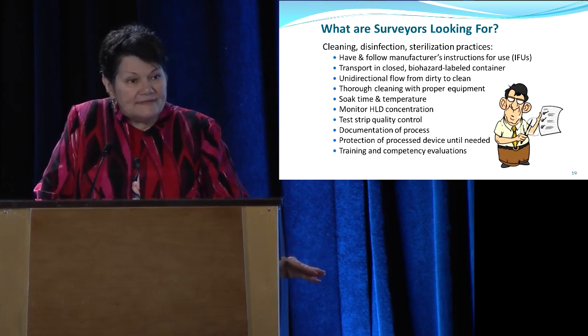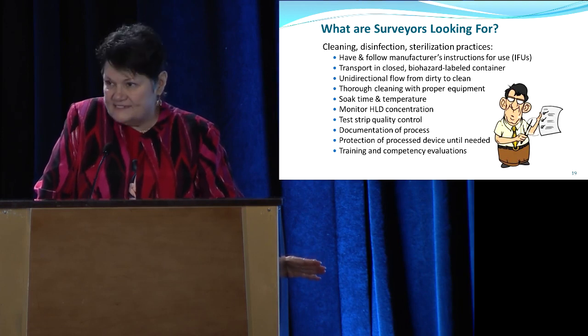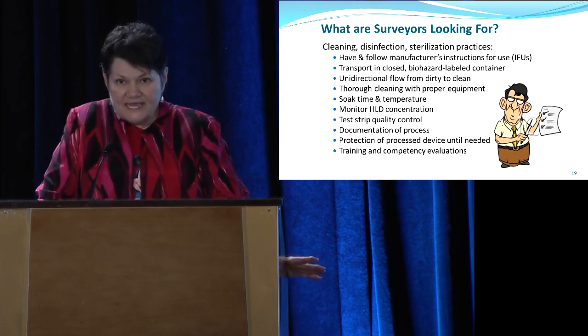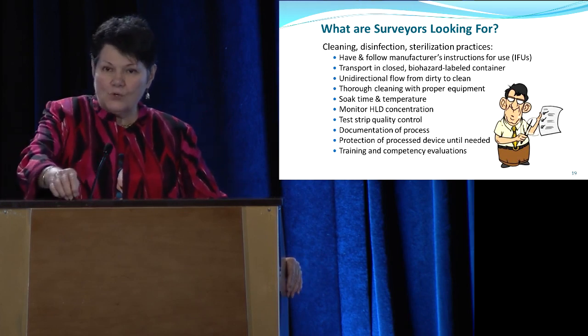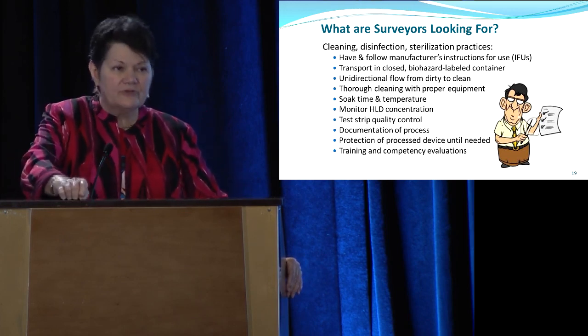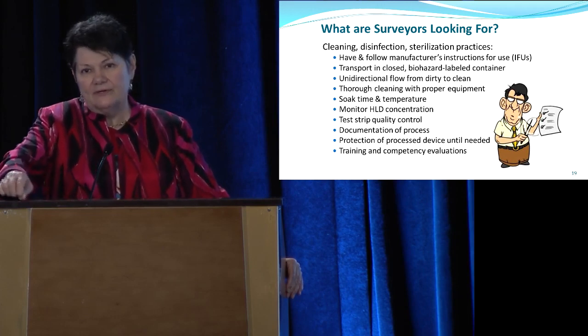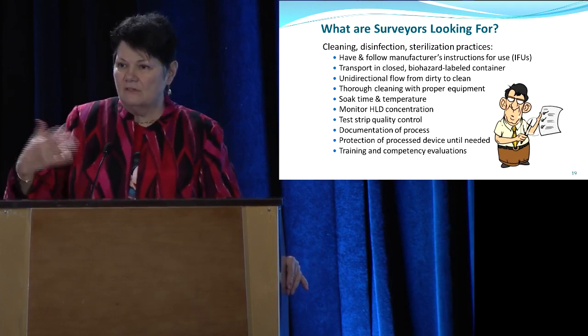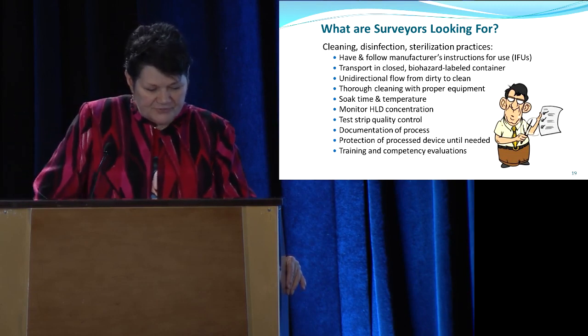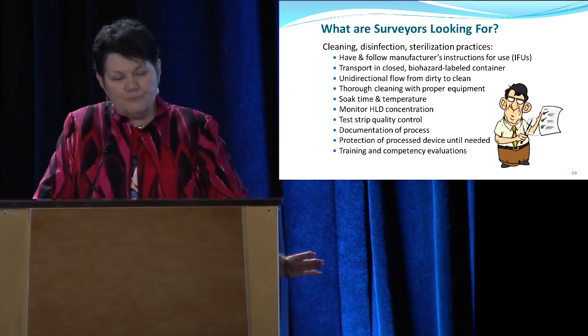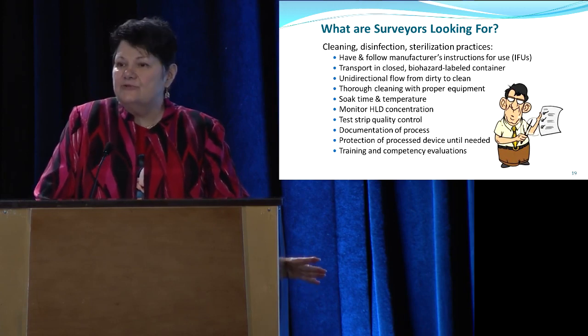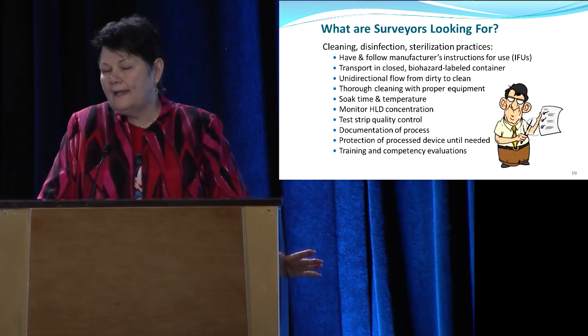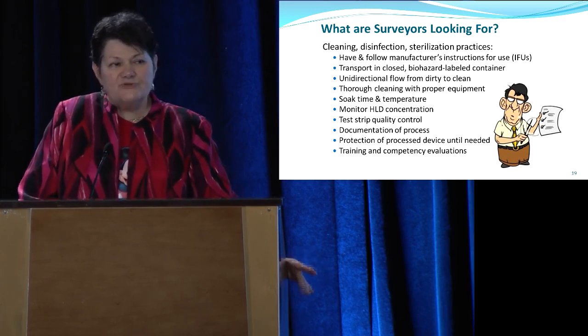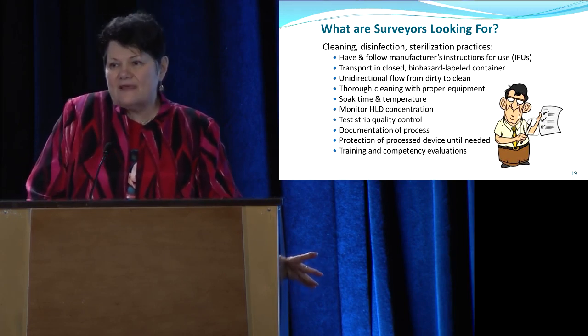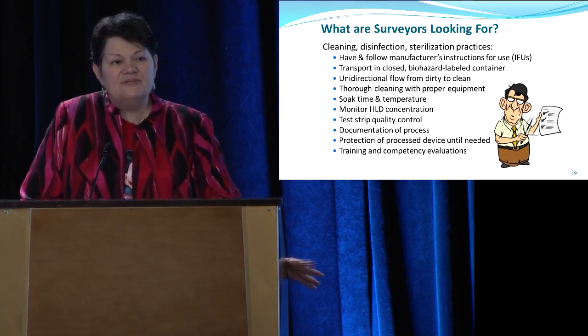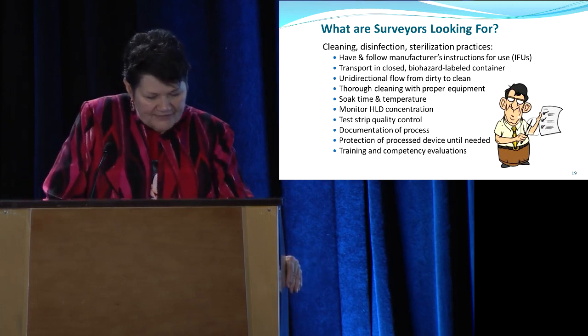So the test strip quality control is another thing I see a gap in. And the documentation process, you need to be recording the time that you put it in, the time for cleaning, the soak time, et cetera, so that you have a log that demonstrates that you're following proper procedures. And you want to protect that processed device. You can put it in a Ziploc bag, you can wrap it in plastic, but Joint Commission especially is looking at this. They want to see things protected between uses, so just be aware of that.